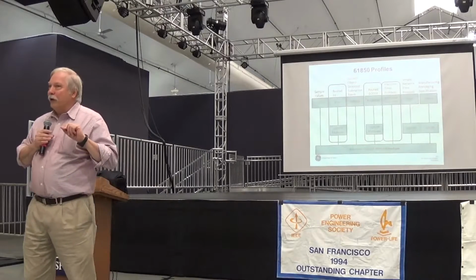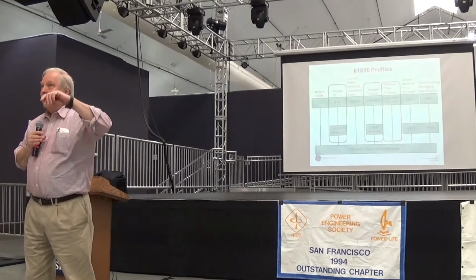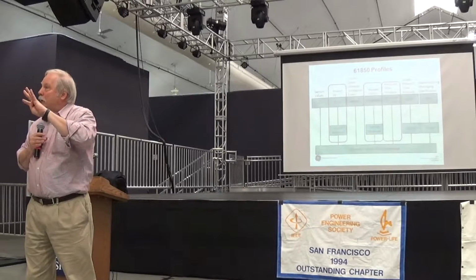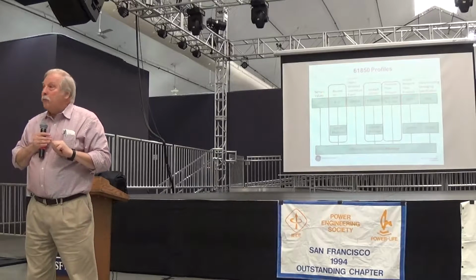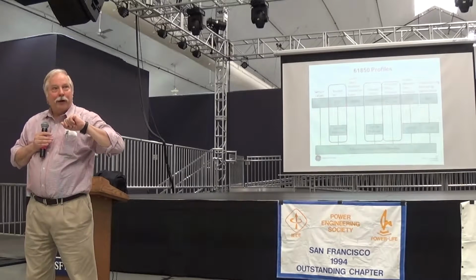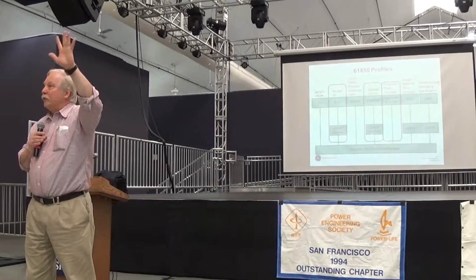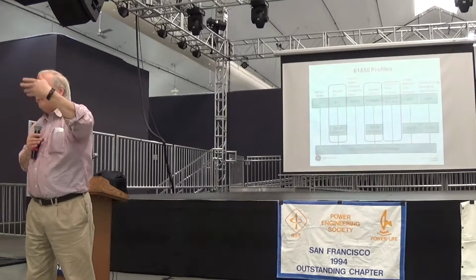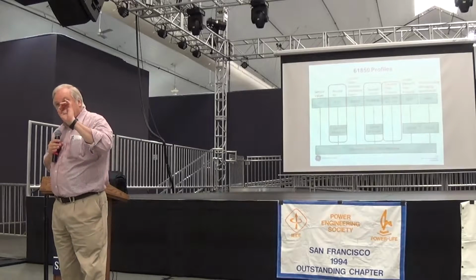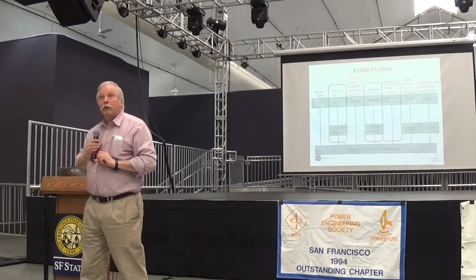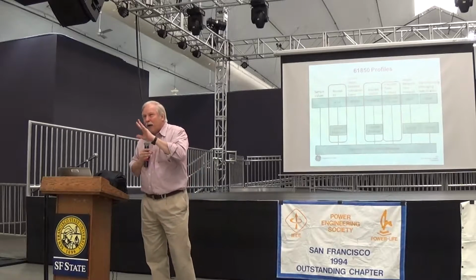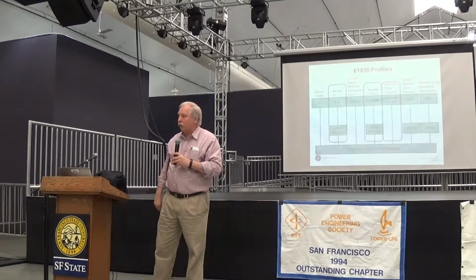So what GOOSE does, it says at time 0, the breaker's open. 4 milliseconds later, it can repeat the message and say, the breaker's open. 8 milliseconds later, it can repeat the message and say, the breaker's open. So by repetition, unless your network is down, that message will eventually get through. That's how GOOSE and sample values, actually sample values not as much, but definitely GOOSE works.